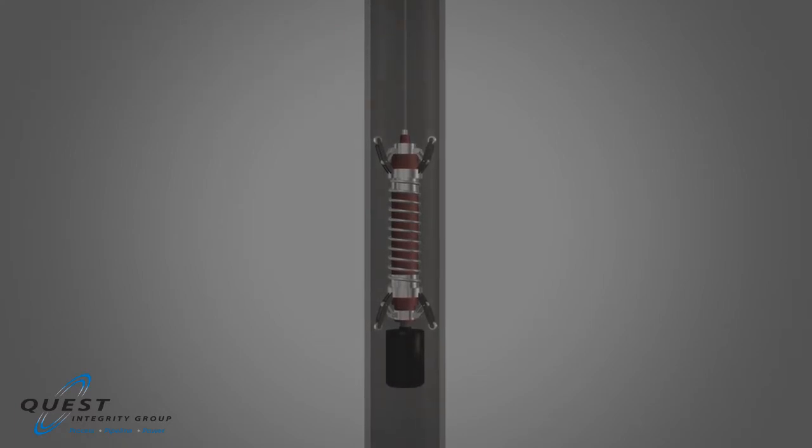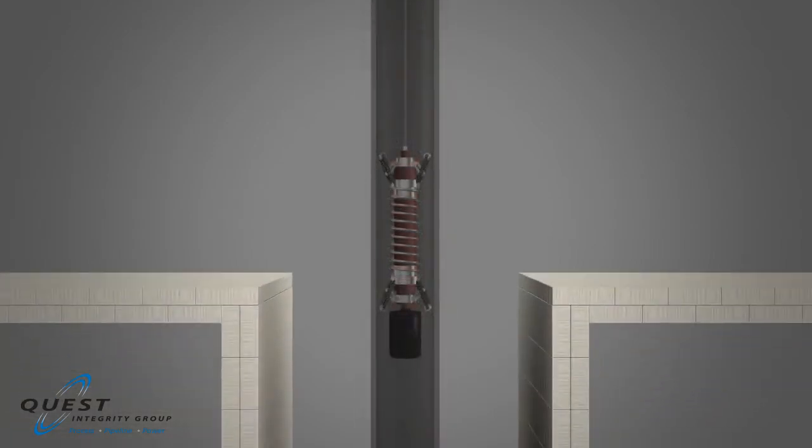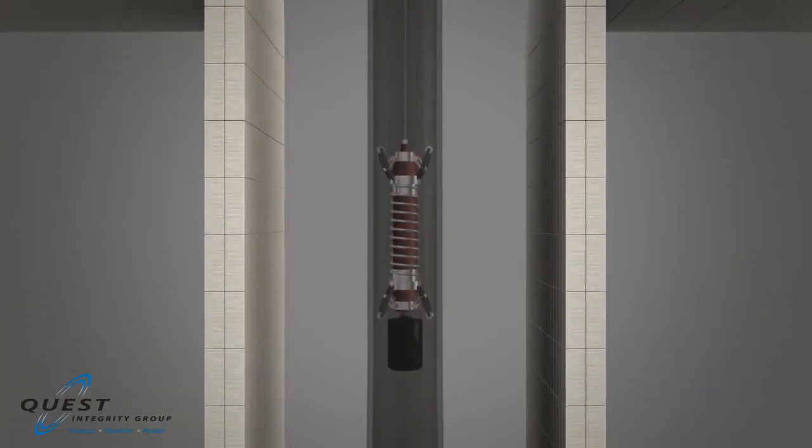LOTIS quickly collects more than 2 million inspection data points over the tube's length and completes the inspection of a single tube in under 3 minutes. These inspections can be performed in parallel with catalyst change-out, with no increase in reformer downtime.